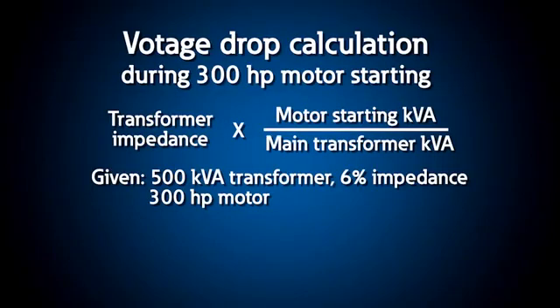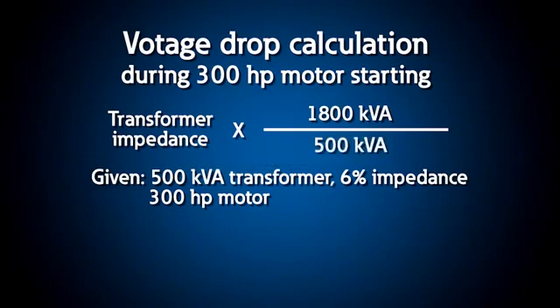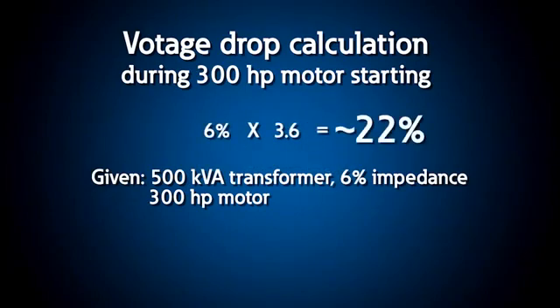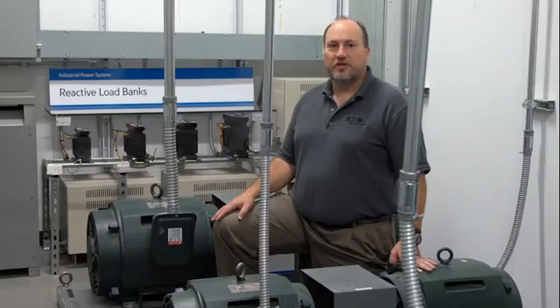This 7.2% change in voltage may cause lights to dim or flicker, but since most loads can endure a 10% voltage change, no formal study is required. For larger motors — say a 300 horsepower motor on the same transformer — the same approach would indicate a voltage drop of almost 22%. This is significant enough to justify a more precise analysis to determine if reduced voltage starting should be considered.